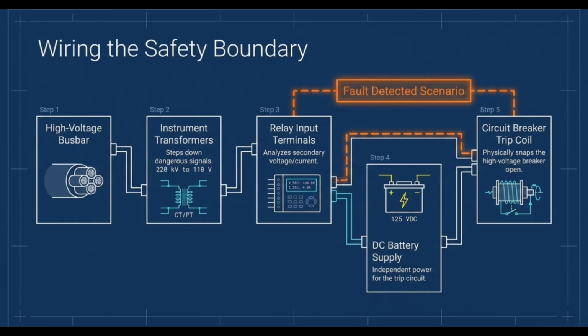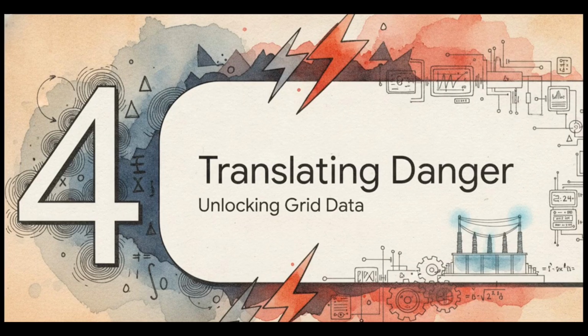And fourth, a completely separate DC battery supply energizes the circuit breaker's trip coil out in the yard. That flexes the mechanical muscle to snap the breaker open and instantly kill the dangerous circuit. All right, let's get into the math. Section 4, translating danger to data, unlocking the grid's secret language.